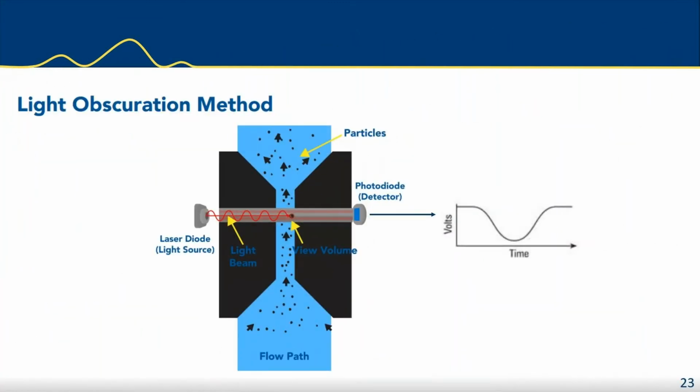And here we have a diagram of a sensor with a particle passing through it. So you notice now what you see here is the laser light is not falling directly onto the photodetector. So you see a reference voltage here dips down.